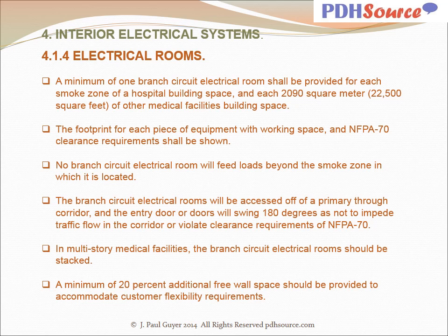The branch circuit electrical rooms will be accessed off of a primary through corridor, and the entry door or doors will swing 180 degrees as not to impede traffic flow in the corridor or violate clearance requirements of NFPA 70. In multi-story medical facilities, the branch circuit electrical rooms shall be stacked. A minimum of 20% additional free wall space should be provided to accommodate customer flexibility requirements.